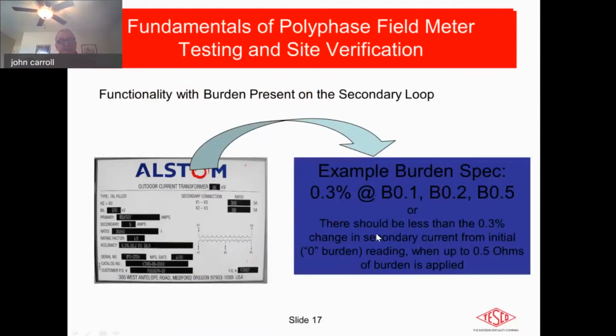Now, we talked a little bit before about some of the basics of the field testing and verification. One of the things I mentioned was the nameplate. This is just one example, no particular allegiance with Alstom, it just happens to be one that we picked. You can see there's a whole range of parameters on here, but the reason that's on there is because one of the key components is a burden specification.